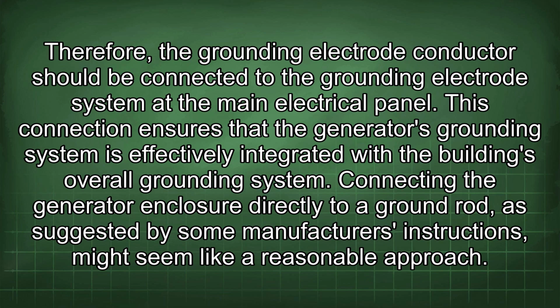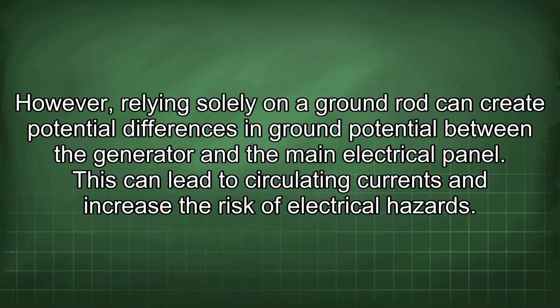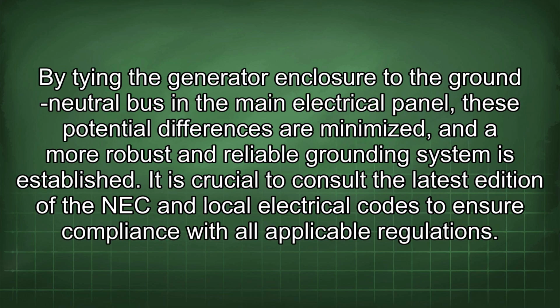Connecting the generator enclosure directly to a ground rod, as suggested by some manufacturers' instructions, might seem like a reasonable approach. However, relying solely on a ground rod can create potential differences in ground potential between the generator and the main electrical panel. This can lead to circulating currents and increase the risk of electrical hazards. By tying the generator enclosure to the ground neutral bus in the main electrical panel, these potential differences are minimized, and a more robust and reliable grounding system is established.